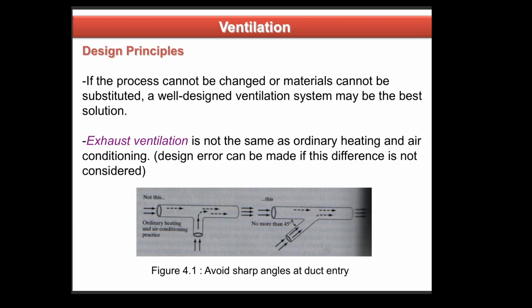Design principles. If the process cannot be changed or materials cannot be substituted, a well-designed ventilation system may be the best solution. Exhaust ventilation is not the same as ordinary heating and air conditioning. Design error can be made if this difference is not considered. You can see the diagram of ordinary heating and air conditioning practice. In the T-junction diagram, sharp edges and a 90-degree bend are there, and in the second diagram you can see a 40-degree bend in the duct system, which is desirable. So we have to use a ducting system like in the second diagram, in which the angle between the two junctions is not more than 45 degrees. We have to avoid sharp edges at duct entry.